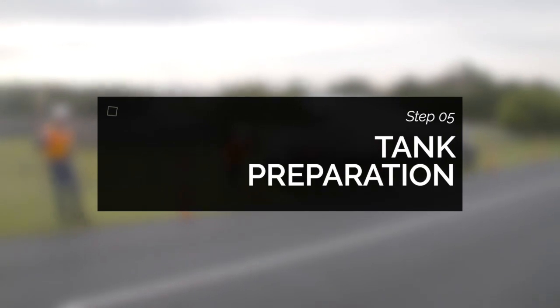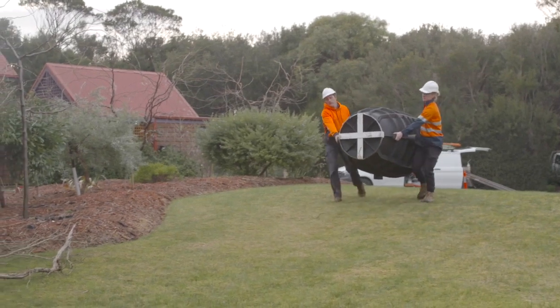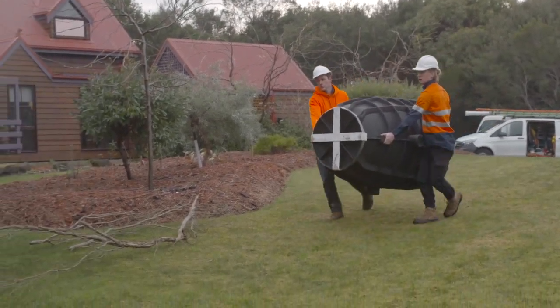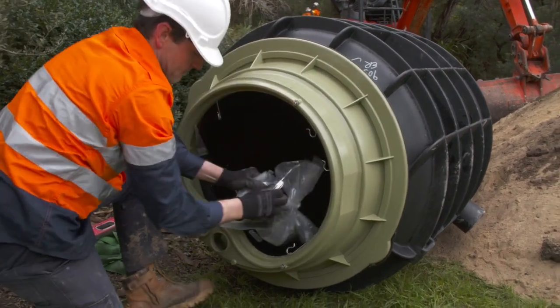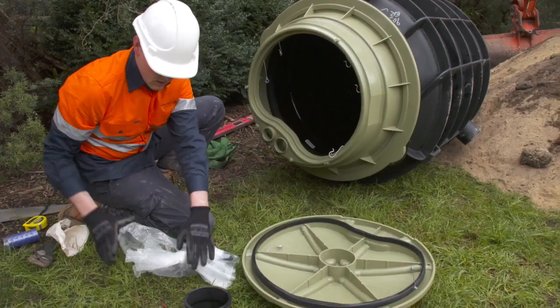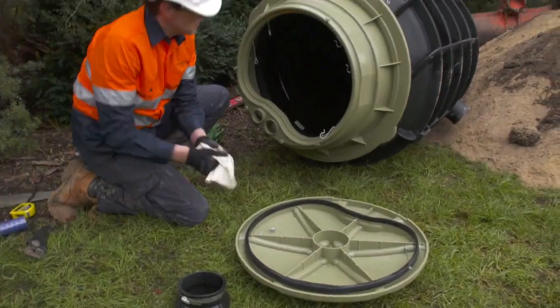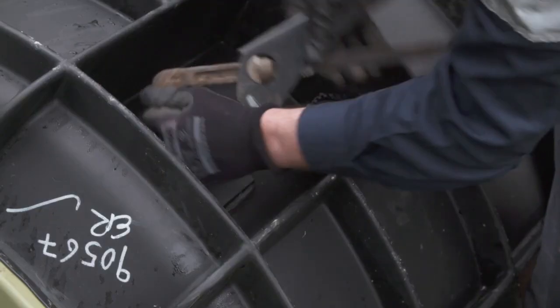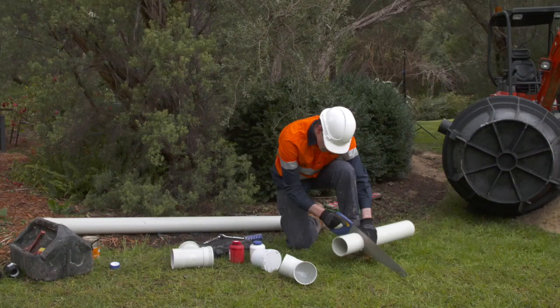Step 5: Tank preparation. The tank weighs 69kg and can be carried into position by two people. The tank includes a 40mm threaded service connection point and three options for 100mm household drain connection. Connection adapters come with the tank. In this case, a 40mm to 50mm adapter is added to accommodate the 50mm service connection.